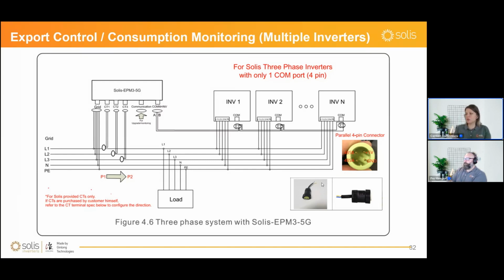But you can also use this 4-pin to parallel the inverters together, so connecting these RS485 pins in parallel and connect them to an EPM. Because of the design of this port, you will actually need this type of adapter. It's an adapter which connects to this 4-pin, and it has 2 wires, the plus and the minus. You have a blue and a yellow. You connect the blues together, you connect the yellows together, and you form your daisy chain, which goes to the EPM. The EPM, as I said, it will stay connected at the grid connection point.